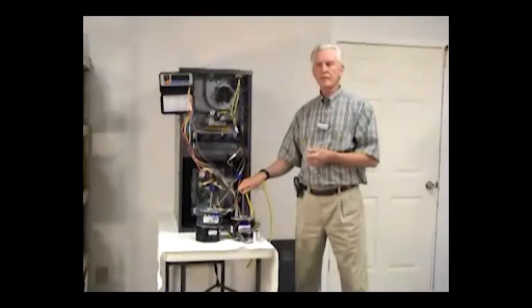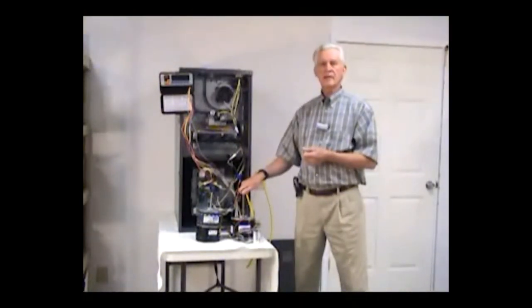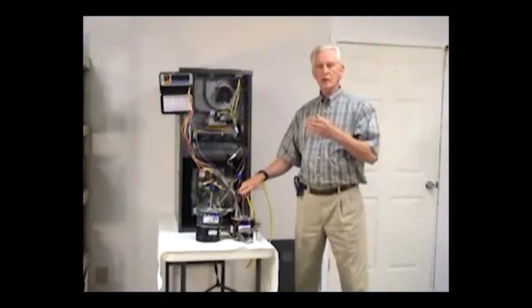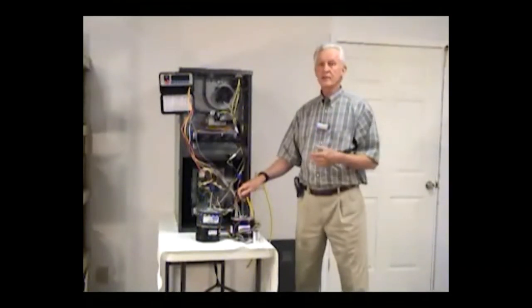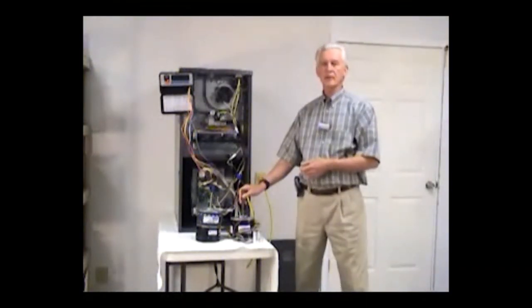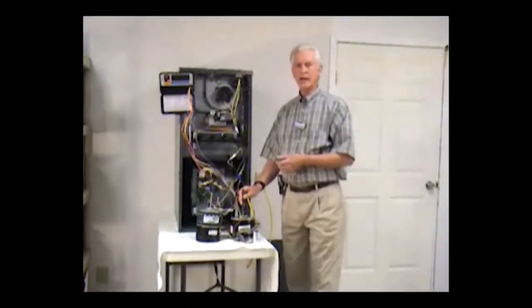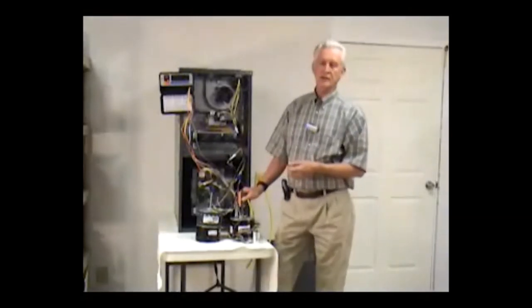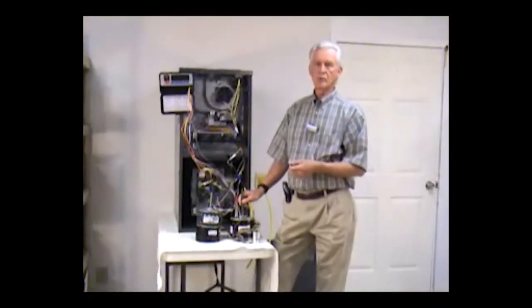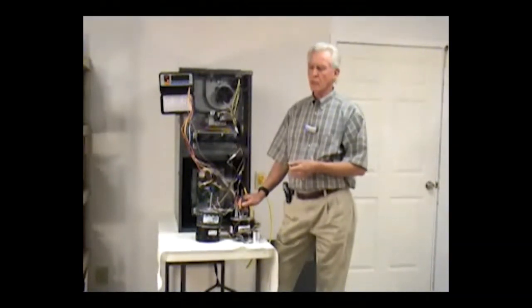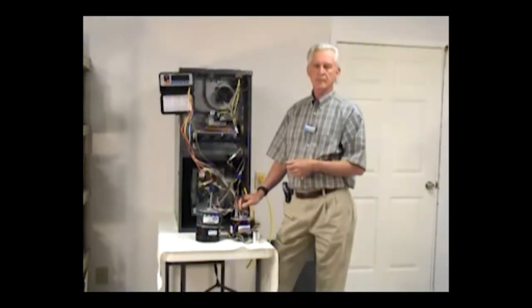Anything past 0.5 for most manufacturers' pieces of equipment, we're going to begin to get a deterioration from, in this case, 3 tons of application, 1,200 CFM. That CFM will actually begin to go downhill. We will start to see a loss as we produce more and more static against that motor. At 0.7 or 0.8, we're probably nowhere near 1,200 CFM at that stage of the game.